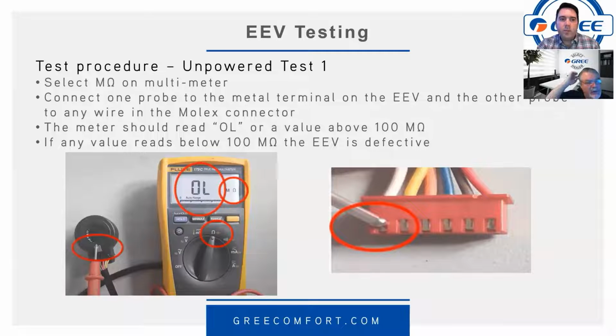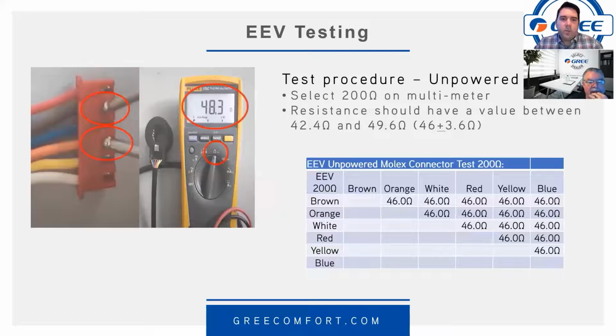But select megohms on the multimeter and put the red lead on the metal tab on the bottom of the coil. Mm-hmm. Is that the tab that holds it on when you twist it? Okay. Yeah, it makes contact. It's a ground tab basically. So you put the tab there, and then you can check across any of the pins in the Molex connector. They should, and we'll spell this out in the manual, but it should all be fine or open. 100 megohms, yeah. And then EEV testing.